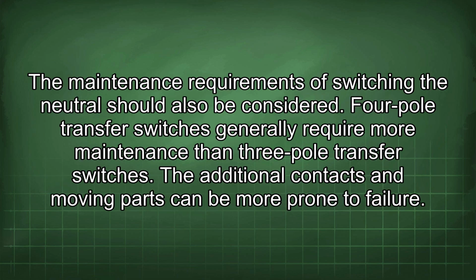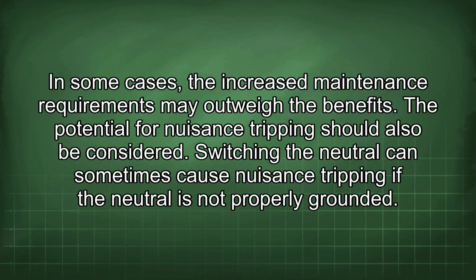The maintenance requirements of switching the neutral should also be considered. 4-pole transfer switches generally require more maintenance than 3-pole transfer switches. The additional contacts and moving parts can be more prone to failure. In some cases, the increased maintenance requirements may outweigh the benefits.